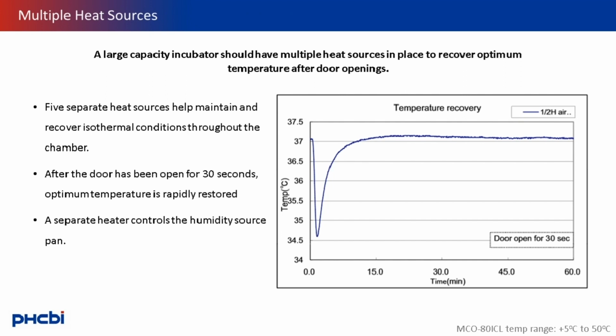As incubator size increases, heat must be controlled and monitored from several different heat sources. A main heater, bottom heater, flange heater, door frame, and door heater all combine to maintain and recover optimal incubation temperatures. After someone has had the door open for 30 seconds, all heat sources act to restore the internal environment's ideal temperature in minutes. A separate heat source for the humidification pan is in place to control the different levels of humidity.